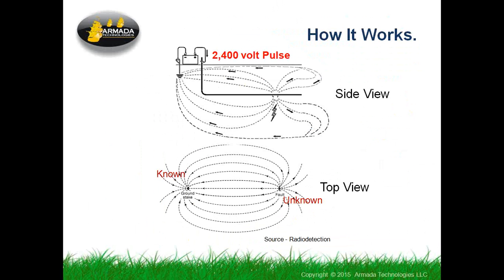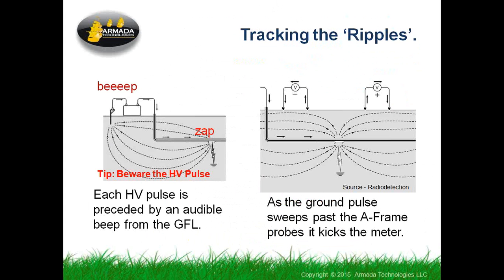It spreads out in a way that lets us tell what direction we are relative to where the thing has occurred. There's a higher voltage setting on the locator that you can use, but it finds the smaller damage. I always recommend we start out with the smallest pulse, which is 2400 volts, and it should find only the larger damage. When you get into chasing down damage on a cable, you can often find that there are multiple places where damage has occurred. It just hasn't become a problem yet, and you're looking for the main one. You might find that a cable has been cut, but somewhere in between where you're starting out and where the cable has been cut, you have a couple places where some damage has been. So be prepared for seeing multiple locations or faults. So the faults are unknown, and that's what we're after here.